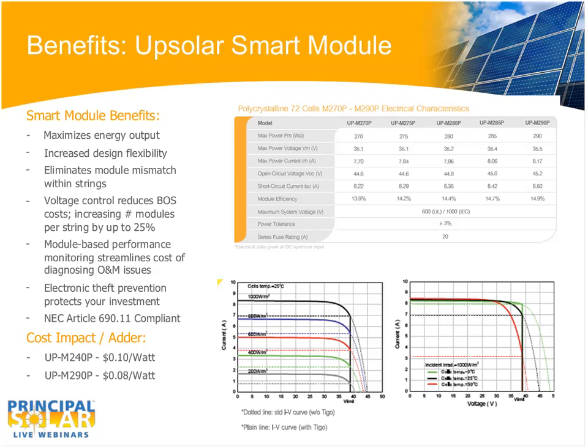What we really like about it as well is that you have module level monitoring, MPPT tracking, and for a project like Talmage, it's going to make the O&M much simpler moving forward. Within the integrated junction box, you've got electronic theft prevention, and it's actually NEC 690.11 compliant and has arc fault protection built into it. The impact is about 10 cents a watt on a 240 watt module, about 8 cents a watt on a 290 watt module or a 72 cell format.